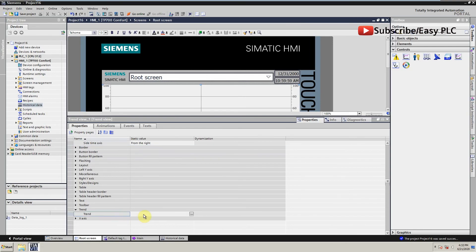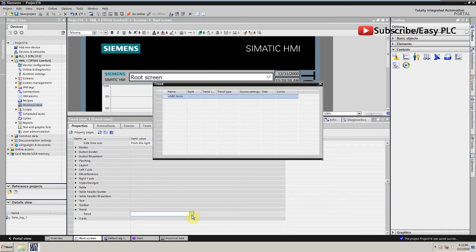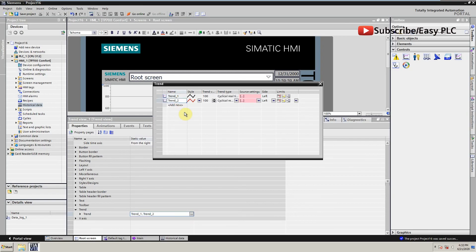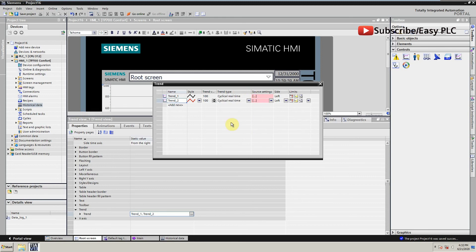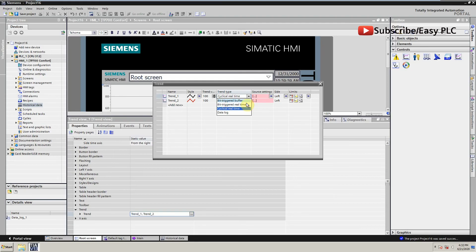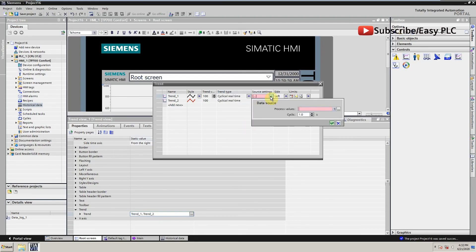From properties we will select trend option and open it. Here we can create the tags we want to show on the trend screen. In trend type we have different options, but we will keep it same as cyclical real time. Now we will select the PLC tags for these two trends.